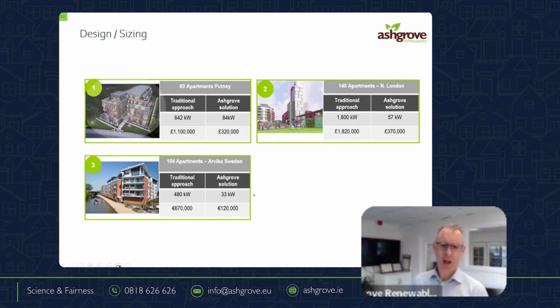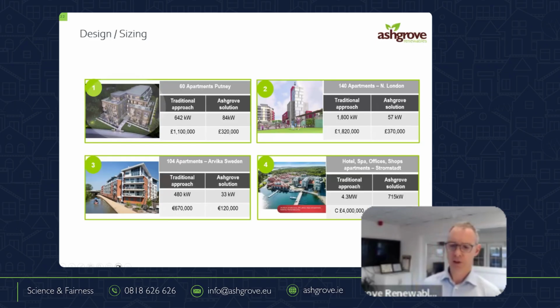We can show all sorts of examples here. We often used to take engineers to apartments in Sweden. It's 104 apartments, and the hot water load was 33 kilowatt. A typical oil boiler in Ireland 10 years ago, for any size of house, was 26 kilowatt. And here we are doing 104 apartments' hot water with 33 kilowatt. And there wasn't a backup. So these are all examples of oversizing because we're using, I'm going to say, prehistoric philosophies for sizing of heat pumps.